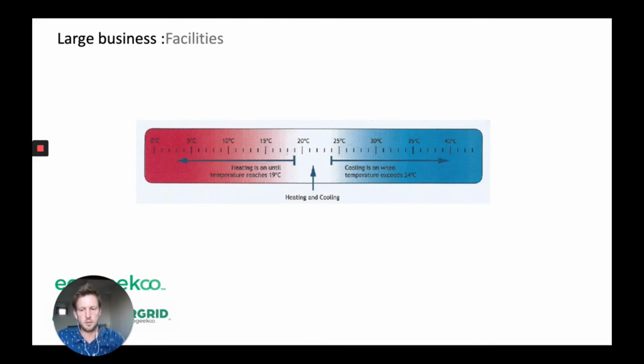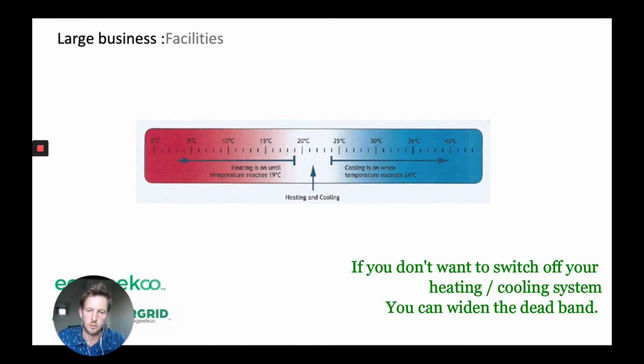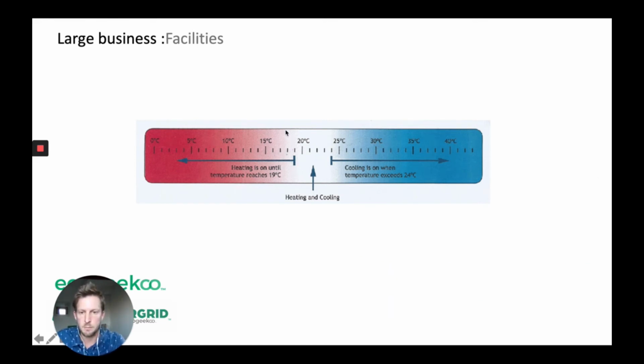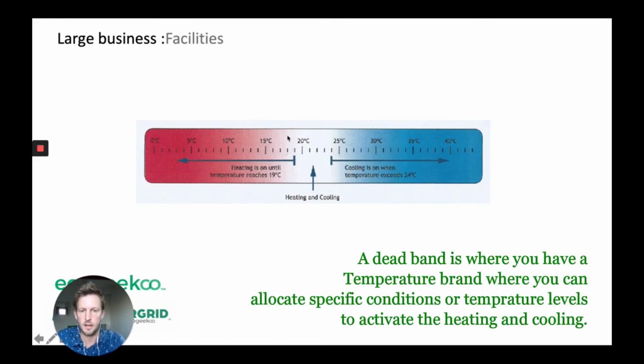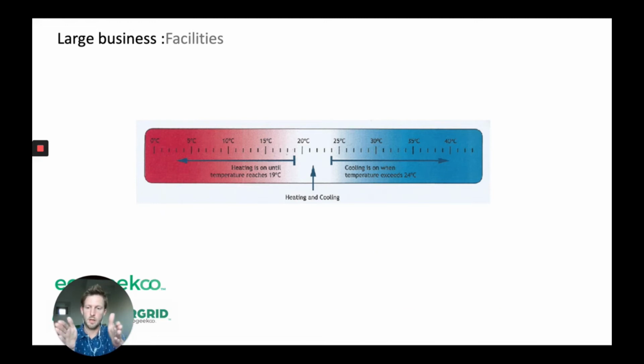If you're a bit nervous about switching off any heating or cooling systems, one thing you can do is actually widen what's called the deadband. So a deadband is where you have a temperature band where you're going to say at this temperature activate the heating and at this temperature activate the cooling. The closer they are, the more your systems are going to be activating to keep what's called a narrow deadband. So it's quite common that we run our offices at, say, somewhere between 21 and 23 degrees.